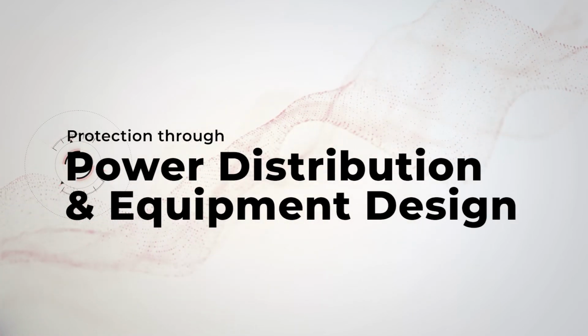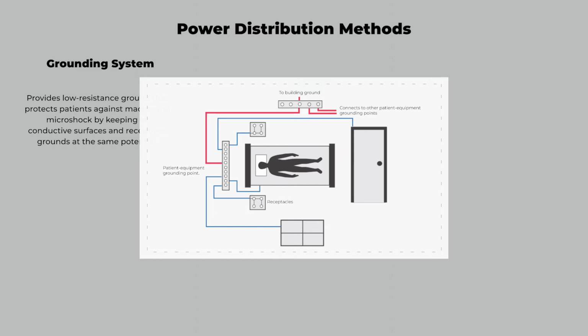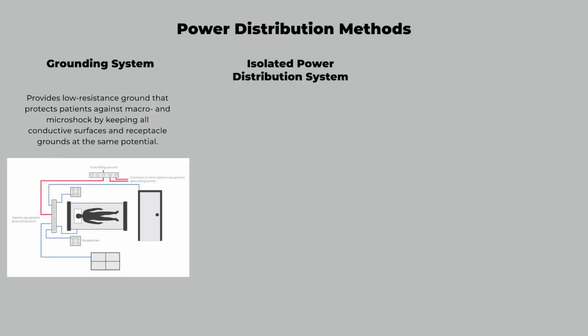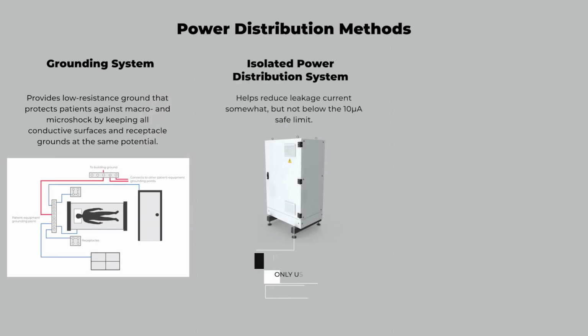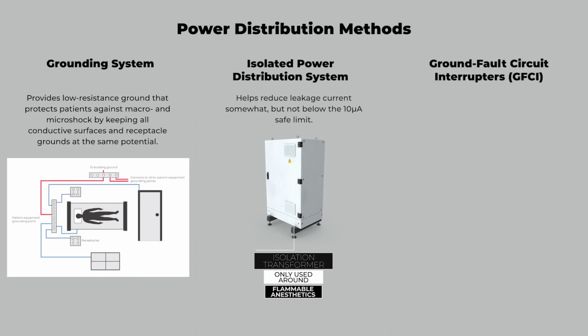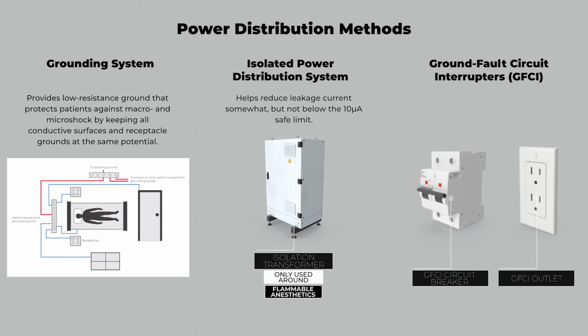Protection against shock hazards can be achieved through power distribution and by equipment design. Power distribution offers three methods. A grounding system which provides low resistance ground that protects patients against macro and microshock by keeping all conductive surfaces and receptacle grounds at the same potential. An isolated power distribution system which helps reduce leakage current somewhat, but not below the 10 microampere safe limit. And ground fault circuit interrupters, or GFCI. These disconnect the source of electric power when a ground fault greater than 5 mA occurs.